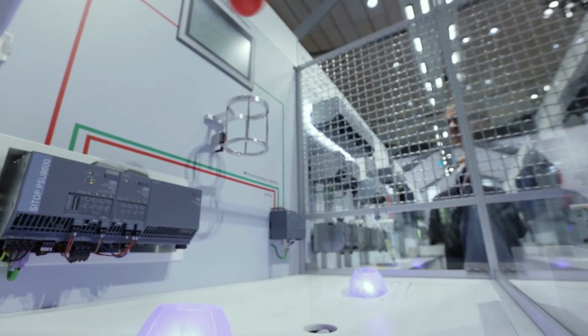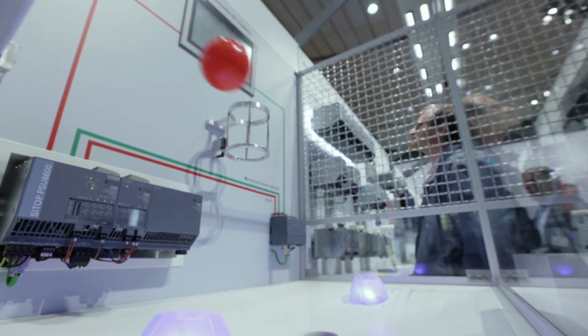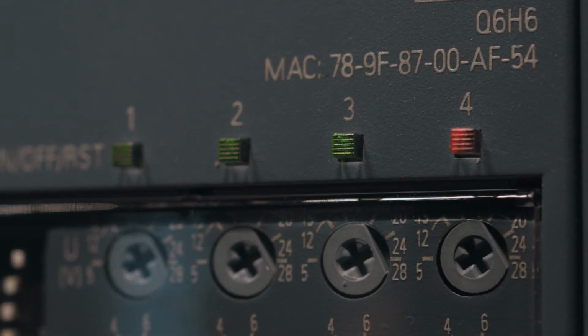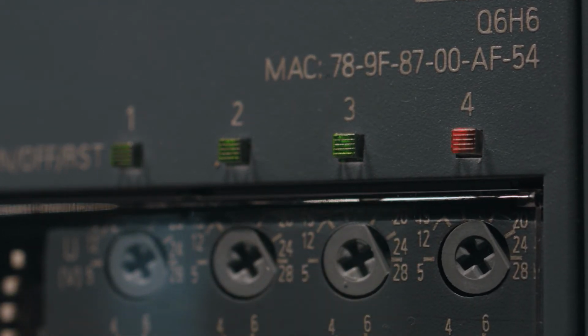Another function is the targeted power up and down of the outlets, in which case we can control a solenoid, which catapults the ball into the airflow. Thus, loads up to 20 amp without PLC output or relay can be directly switched in a plant. In order to reduce energy, consumer branches can also be directly turned off using, for example, the Profinet Energy Protocol.